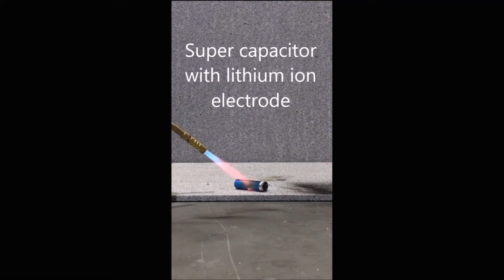So you see it'll start venting soon when it bursts open. It's venting because it's so hot, it's hitting probably close to 1,000 degrees, and the electrolyte's evaporating and coming out, and it's burning in the flame, then it just self-extinguishes. If you take the flame away, it puts itself out.